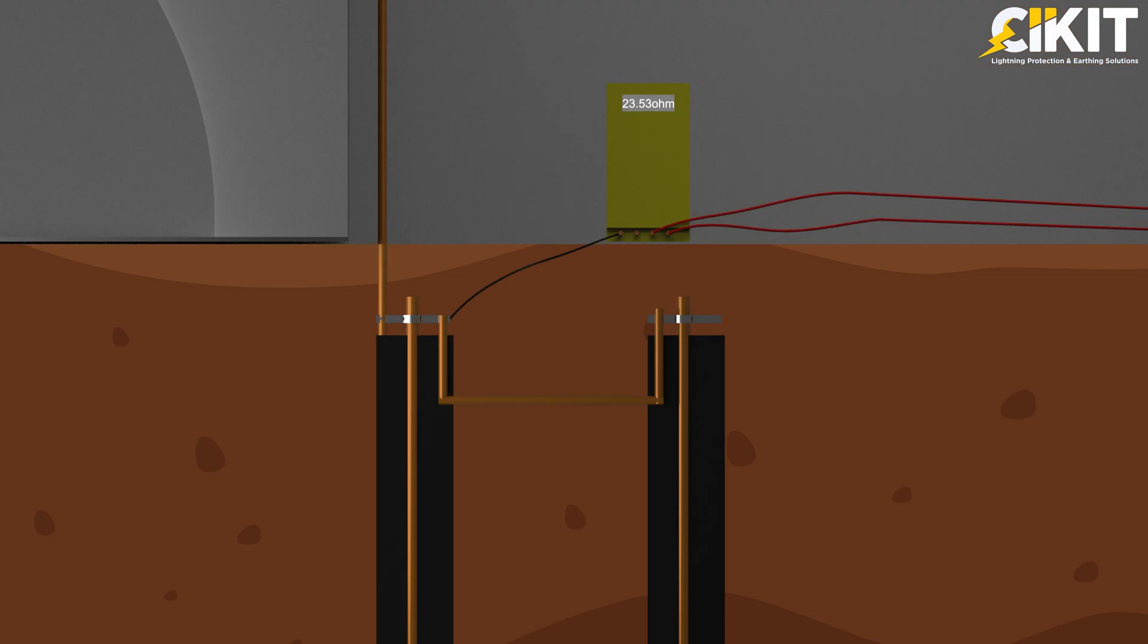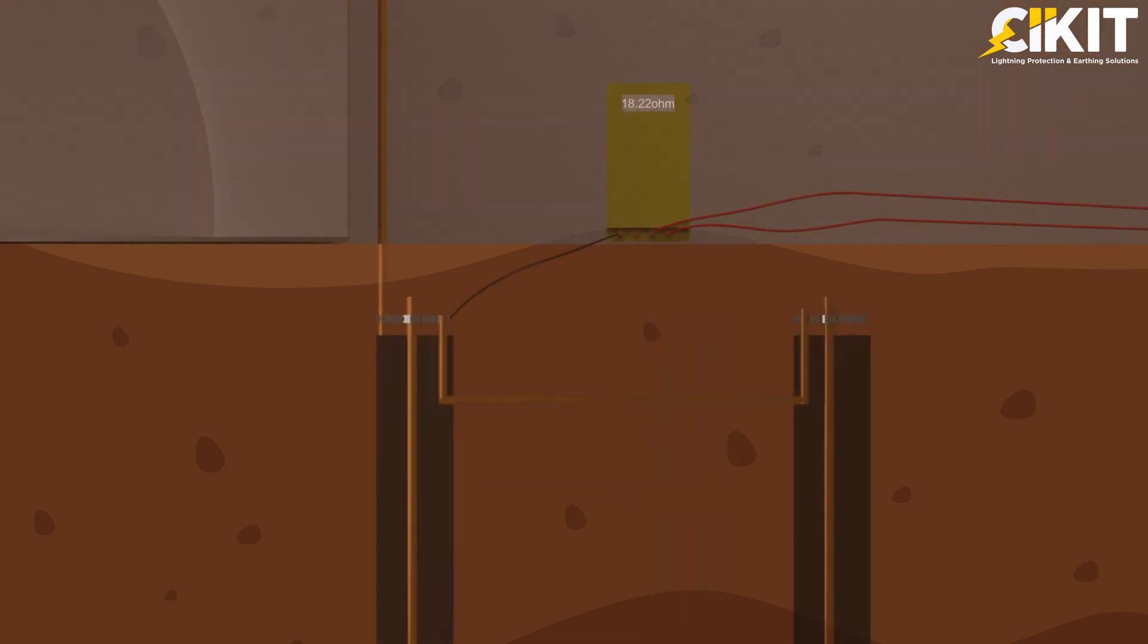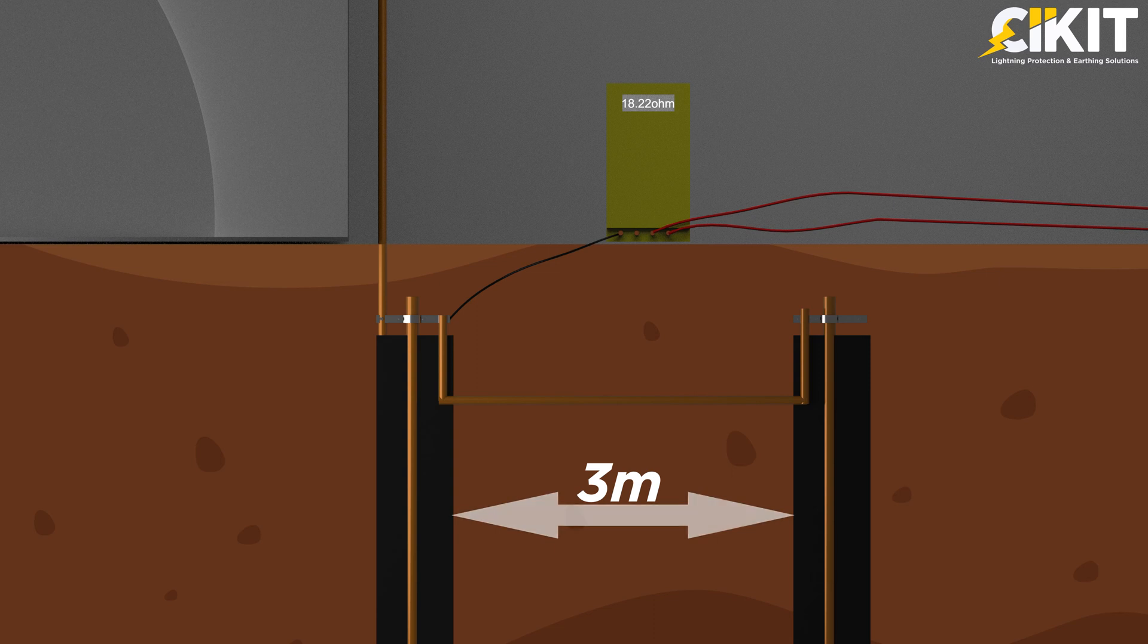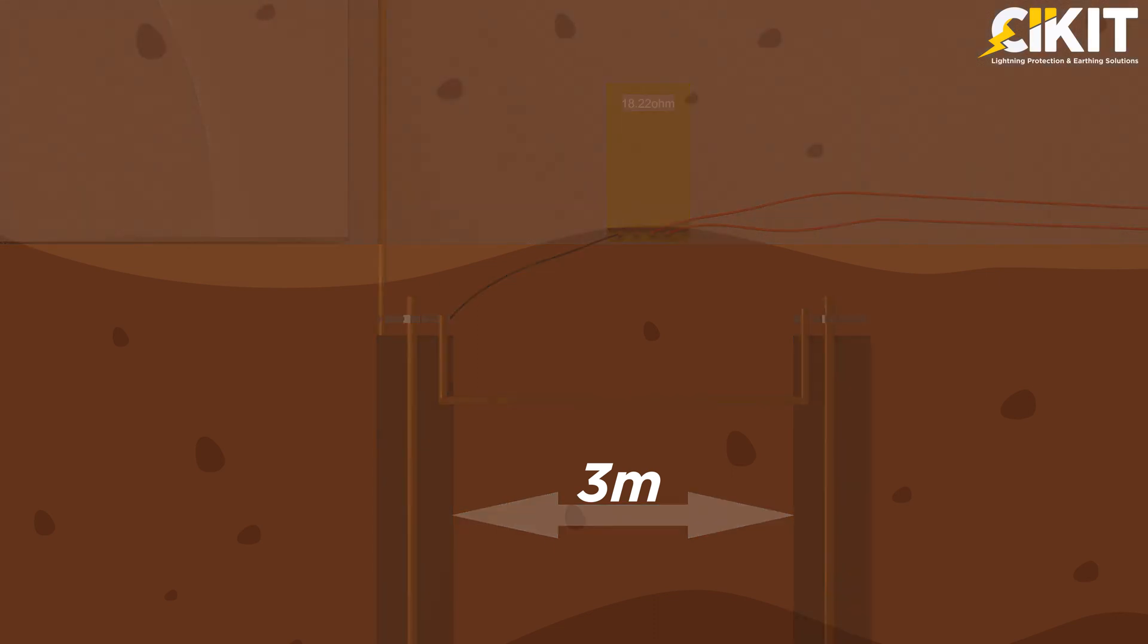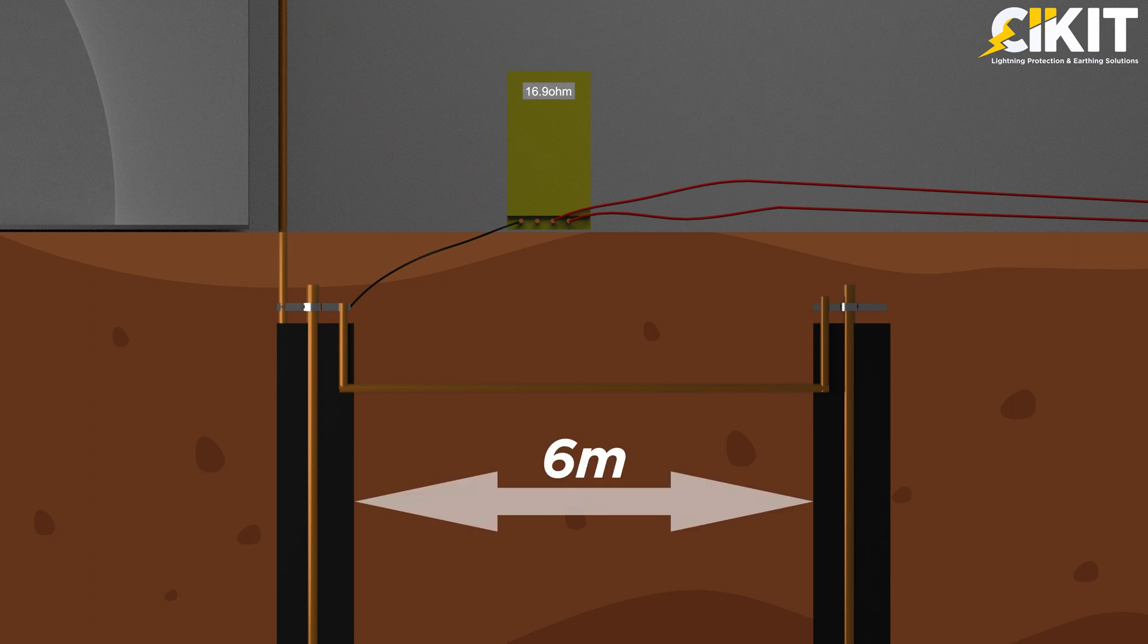If the spacing between two earth electrodes is 1 meter, then the combined resistance value is 23.53-ohm. If we increase the spacing to 3 meters, then the combined resistance value is 18.22-ohm. If we further increase the spacing to twice the length of the electrode, 6 meters, then the combined resistance value will be 16.9-ohm.